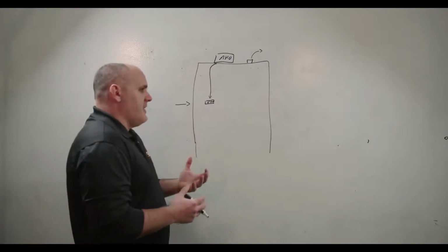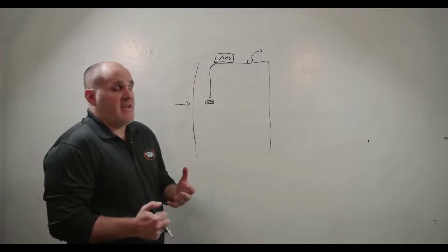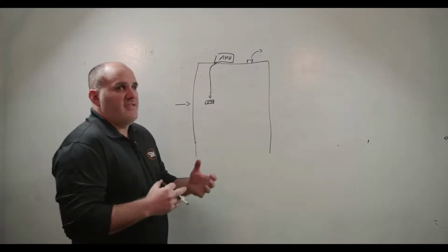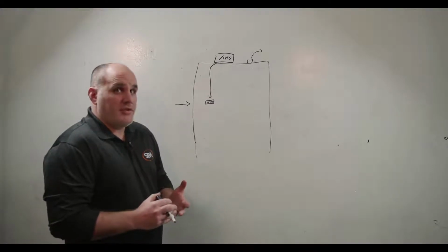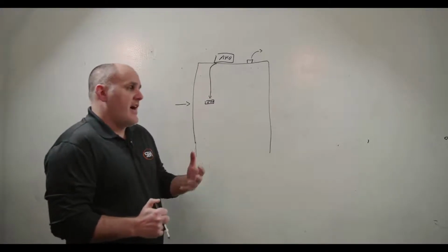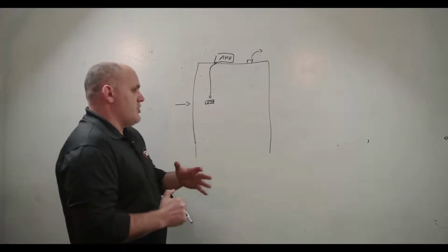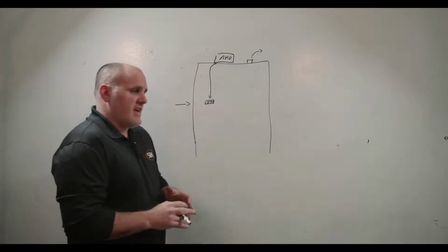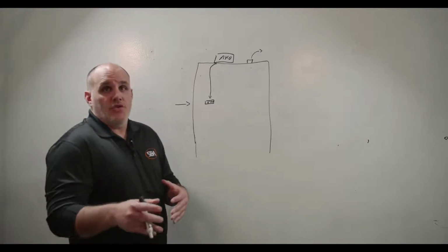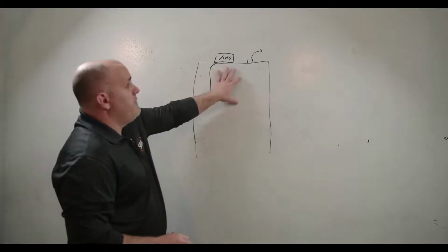I personally like volumetric offset as my preferred strategy. I like to do that. I feel it gives a better granular level of control. It is definitely more difficult to drive building pressure with a volumetric offset than it is to just drive straight to the set point or to just set and forget doing speed matching.